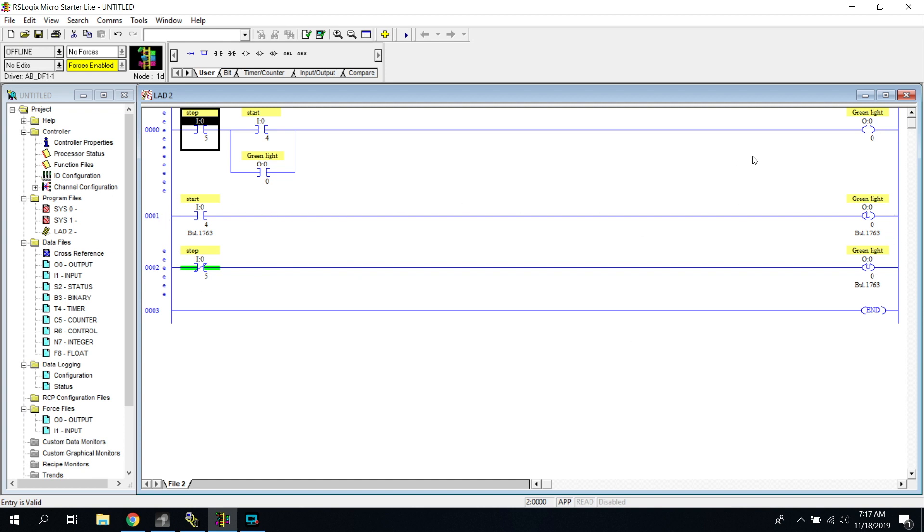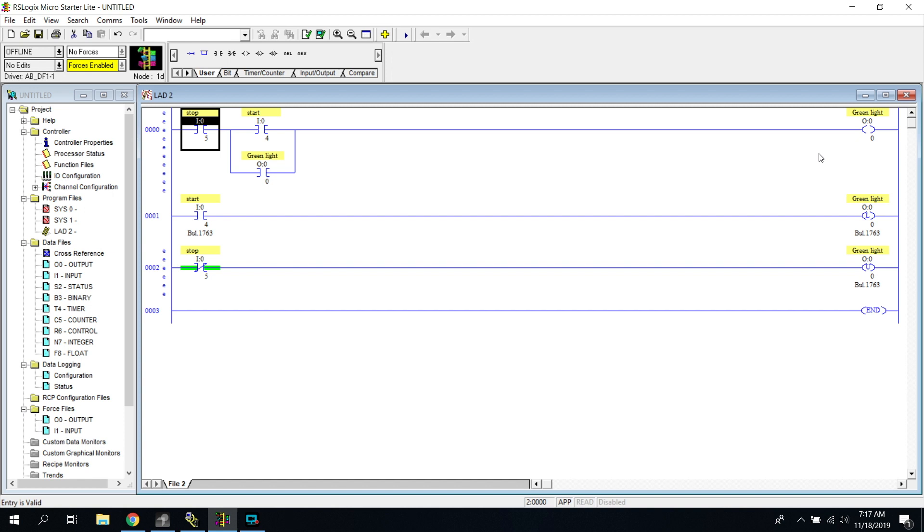But this one is what they call conditional. So it is conditional amongst these instructions right here to be turned on. It's not going to be latched on and held on. And then if something, a wire gets cut or something to a button, it's not going to keep running.